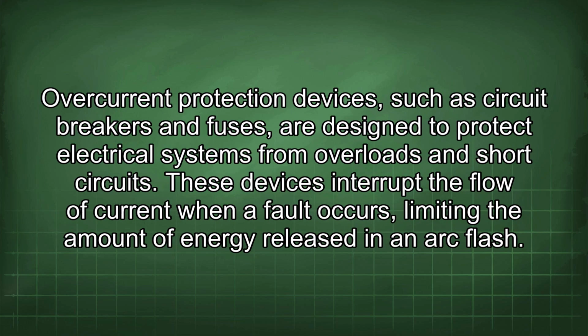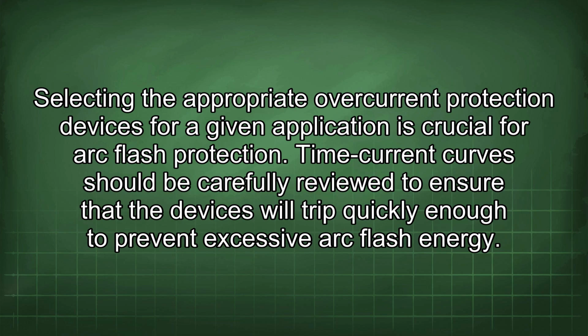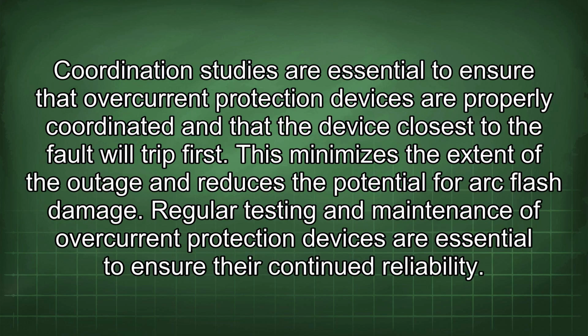Overcurrent protection devices, such as circuit breakers and fuses, are designed to protect electrical systems from overloads and short circuits. These devices interrupt the flow of current when a fault occurs, limiting the amount of energy released in an arc flash. Selecting the appropriate overcurrent protection devices for a given application is crucial for arc flash protection. Time-current curves should be carefully reviewed to ensure that the devices will trip quickly enough to prevent excessive arc flash energy. Coordination studies are essential to ensure that overcurrent protection devices are properly coordinated and that the device closest to the fault will trip first. This minimizes the extent of the outage and reduces the potential for arc flash damage. Regular testing and maintenance of overcurrent protection devices are essential to ensure their continued reliability.